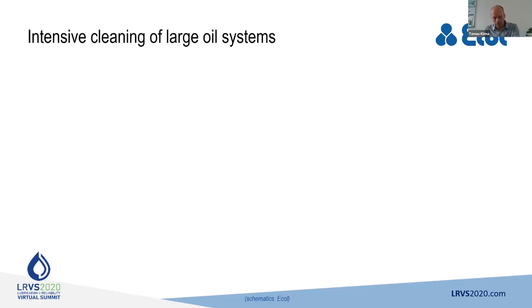So I go to the point of my presentation, how to clean the system. We can clean the system either by chemicals, some pickling. We can clean the system with purification units, which takes time and it has some limits. We can clean, of course, with some detergents or cleaning fluids, where we need to pay attention to cross-contamination, and usually looking for another flushing with flushing fluid before putting in the operation oil.